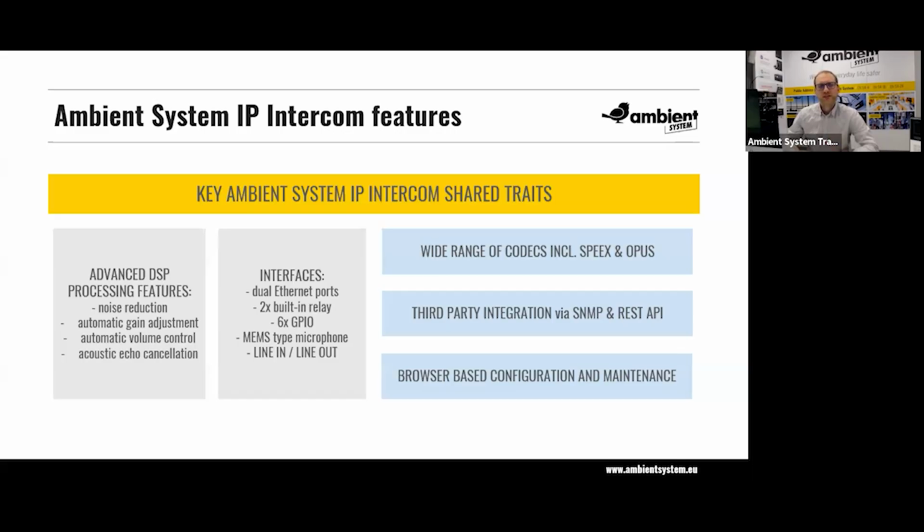Of course, we also have SIP speakers available in our portfolio. The thing about those speakers is that they are regular speakers from our portfolio for PAVA, T2550, W6 or S206. You can see on the screen there is an S at the end of each of them. That means SIP. Each of them is equipped with an amplifier of up to 50 watts, but they are limited. Of course, the 50 watts is available only for the horn speaker, and for the wall-mounted and ceiling-mount speakers, 6 watts is available due to the type of speaker they are built on.